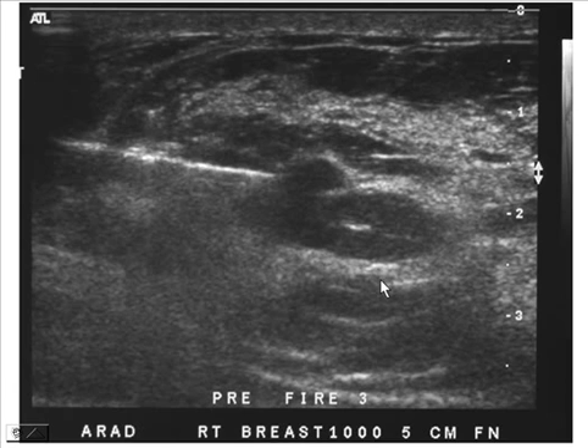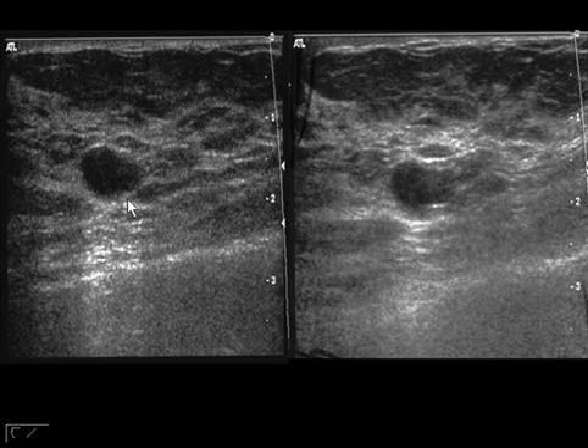Here's one of the disadvantages of compound imaging. Here's conventional imaging where you see this mass, although, as I said earlier, this actually isn't what I'm going to call a cyst because it doesn't have totally smooth margins, but it does have enhanced through transmission. In compound imaging, the enhanced through transmission, the clear band of it that you see here, is made a little less apparent. So if you do have compound imaging on your ultrasound machines, you're going to want to use it for marginal analysis, but then take it off and use conventional ultrasound to show whether or not there is enhancement.